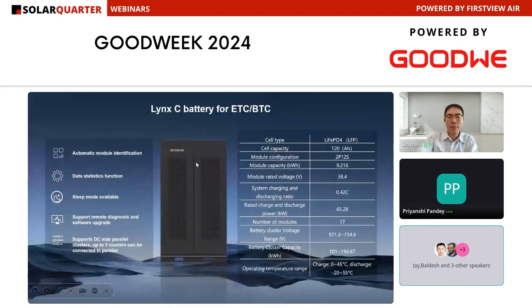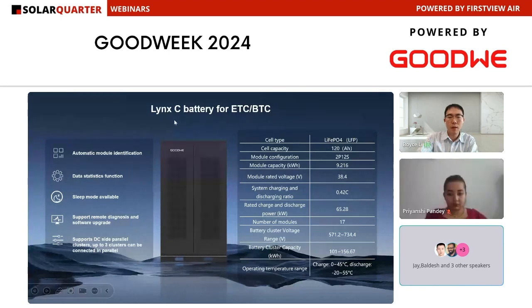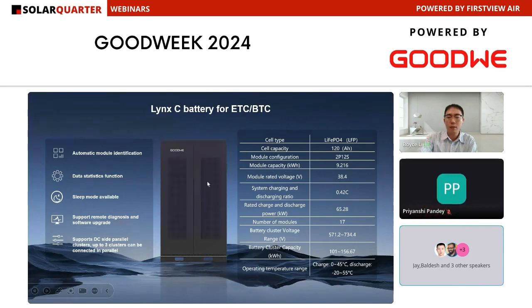The battery that BTC and ETC series can be compatible with is our Lynx series, the Lynx C battery. It's a whole rack using lithium battery cells with a capacity of 120. Each module inside is extendable, at about 9.216 kilowatt hours per module, with a maximum of 17 modules supported. The battery cluster can range from 11 to 17, making it extensible, and the whole system runs at 0.42 C rate.